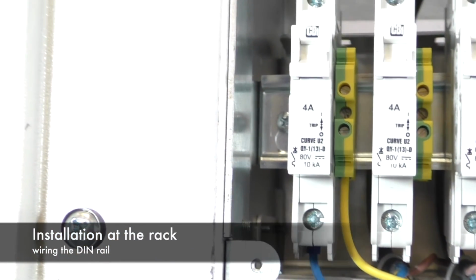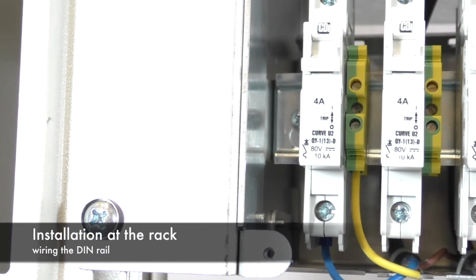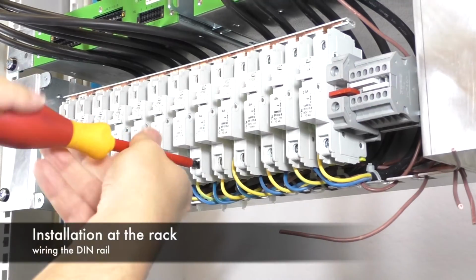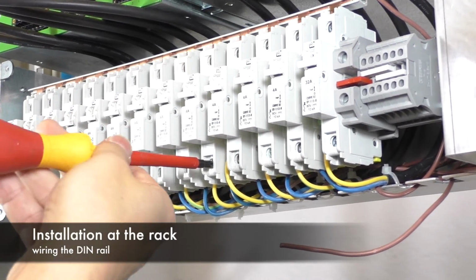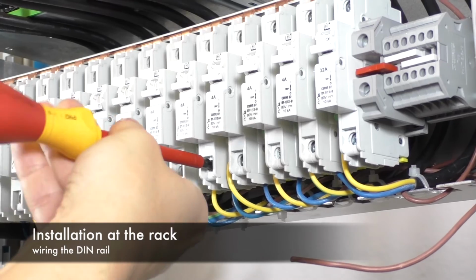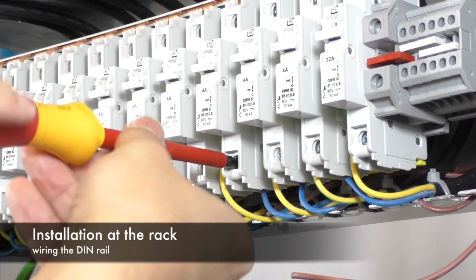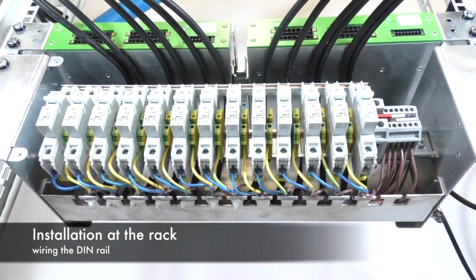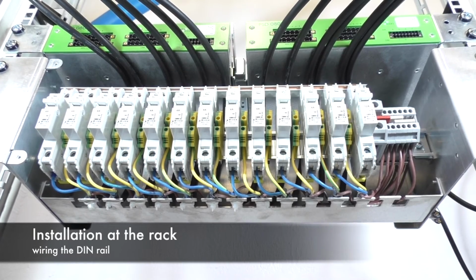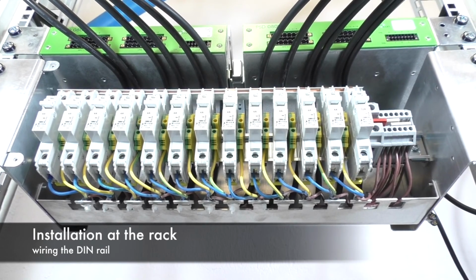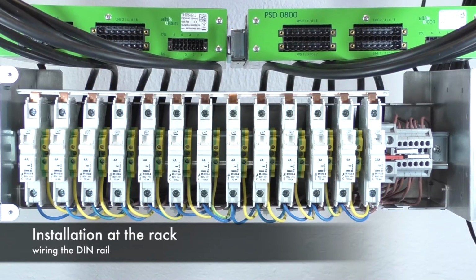Now connect the blue core cables to the circuit breakers and the yellow-green core cables to the terminal blocks. Repeat this procedure with each of the 12 power cables. Connect the brown core cables to the small feed-through terminals on the right-hand side. Finally, connect the 48-volt access line.